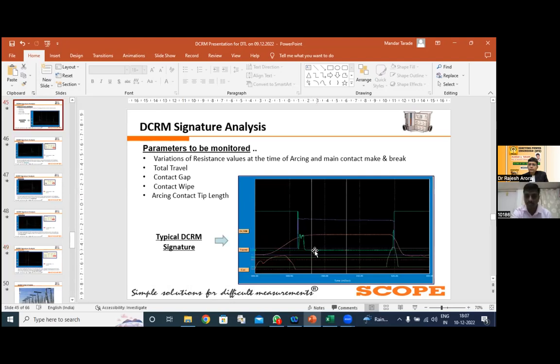If you keep the cursor on the steady position, then you get the value of your static contact. And one more important thing I want to highlight: if you require arcing contact analysis, it's my sincere and humble request to all of you that we do the arcing contact analysis at the time of tripping. Why? Because at the time of closing we observe a number of bounces, and we cannot properly comment on the health of the arcing contact. Whereas in tripping, we take out the entire energy, so we are not expecting any bounces. So if we analyze the arcing contact at the time of tripping, it gives you the correct insights and the correct significance of the arcing contact.